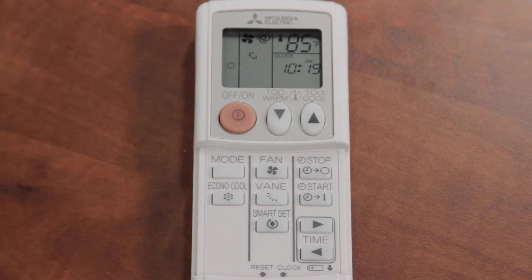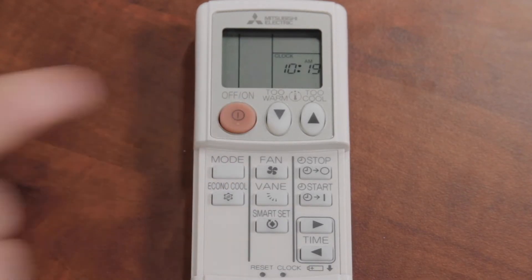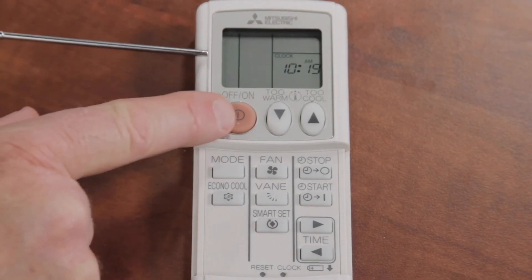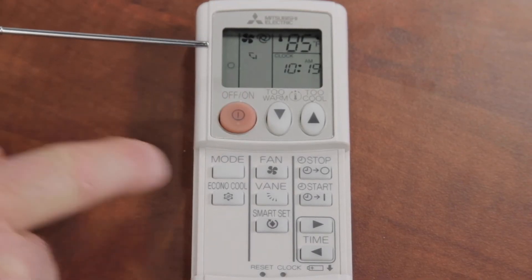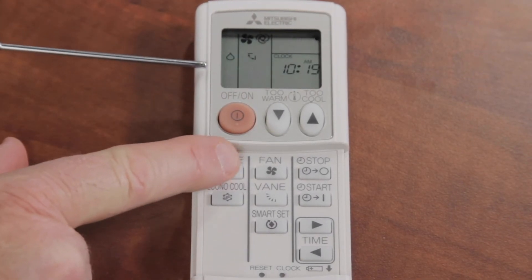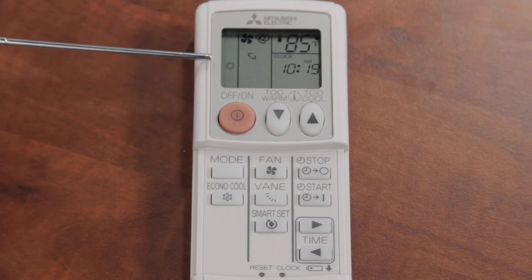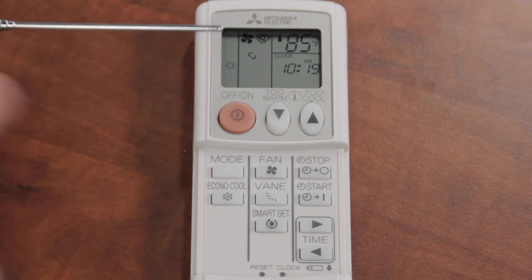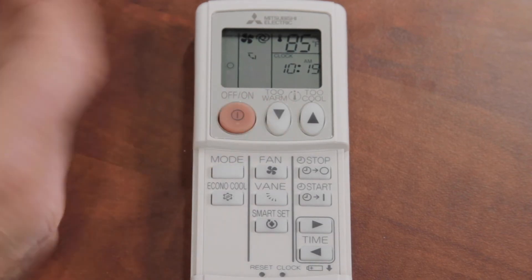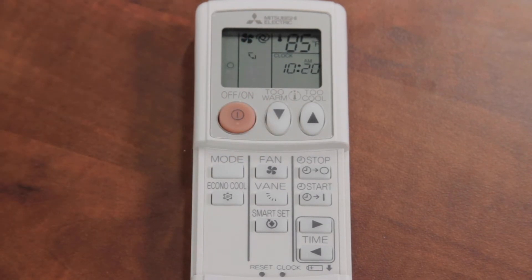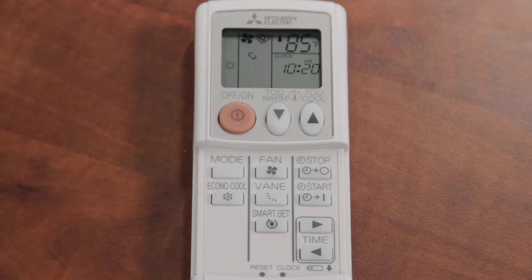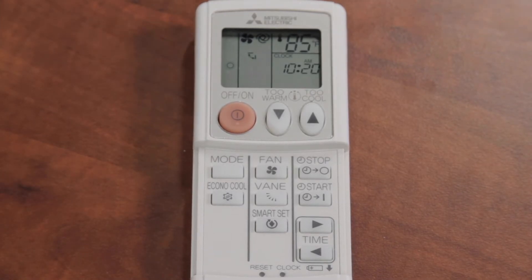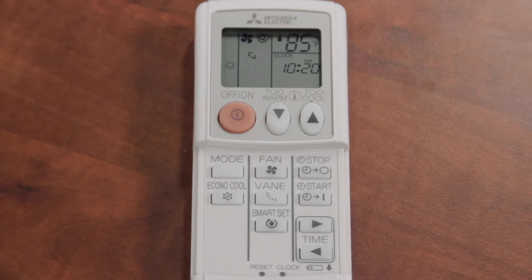This is a very common problem in the wintertime. Someone's one other unit might be in the cooling mode, which shows the snowflake on one of those and where it should be in the heating mode with the sun. So we asked the homeowner to go around, turn all the units off. You can see everything goes off on the remote, turn them back on, and let's put them all into the heating mode, which is the sun. Get them all in the heating mode, and then you can do what you need to do. So that's one of the types of calls we get a lot that we like to walk people through.